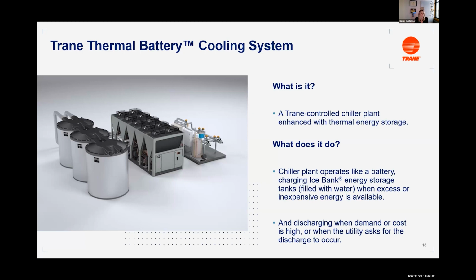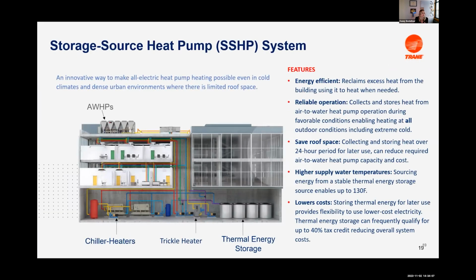It is a complex system that would probably take an hour to explain, which I clearly do not have, but it's a really cool new system where we're looking at the whole system and trying to find ways to reduce wasting heat. So we're trying to save that heat for our buildings to heat and cool. It also allows us to mitigate some of the issues that come with low ambient temperatures and heat pumps. Here's a diagram of what you would need. You need your thermal energy storage, which are your batteries, so your tanks for your heating and cooling ice, possibly a trickle heater if you're in a very cold climate, and then your chiller heaters and your heat pumps. And it's a really cool system.